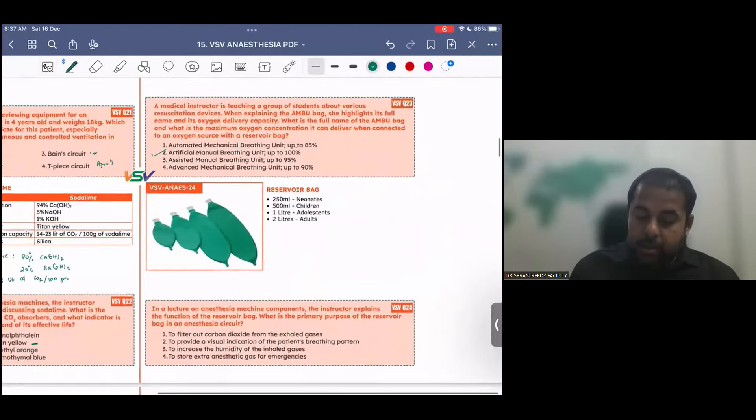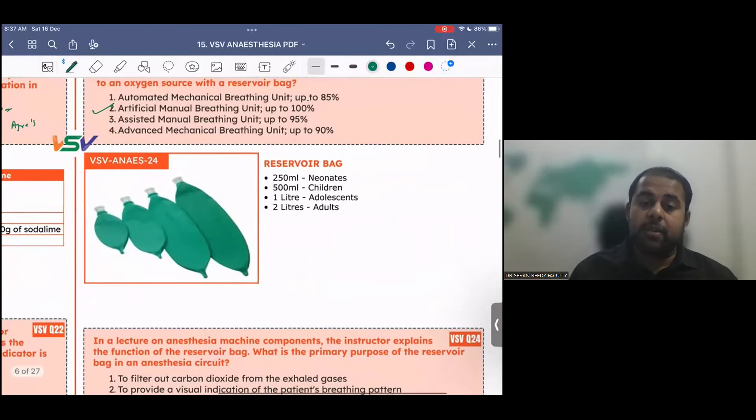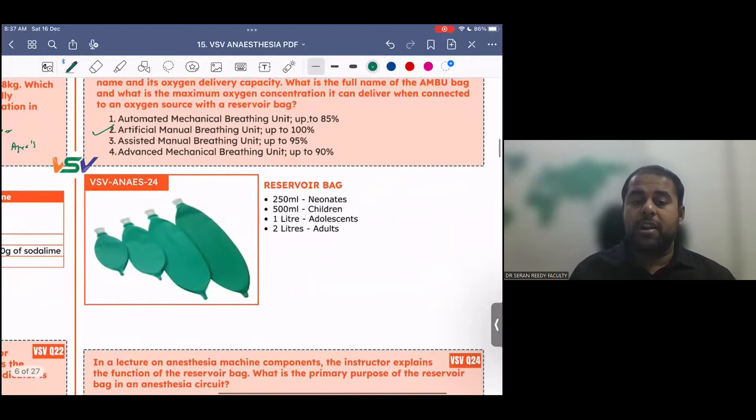This is reservoir bags. There are usually four sizes, 250 ml for neonates, 500 ml for children, 1 liter for adolescents, and 2 liters for adults. What is the use of this? During spontaneous ventilation, whether the patient is breathing or not, you can visually see, based on this reservoir bag. And among the controlled ventilation also, once you keep it, how the bag is moving, it helps giving an idea whether the patient is breathing or not.